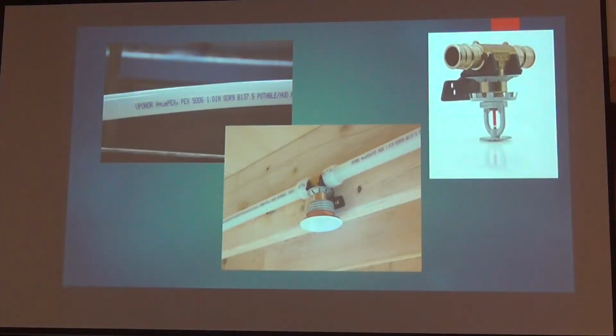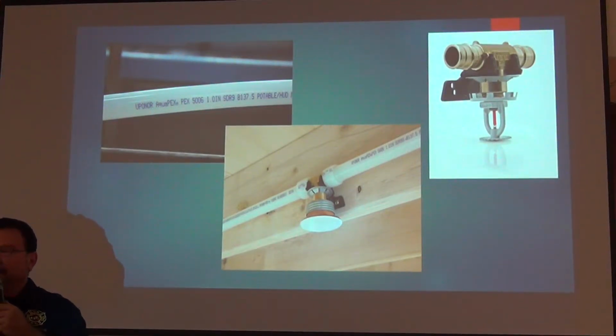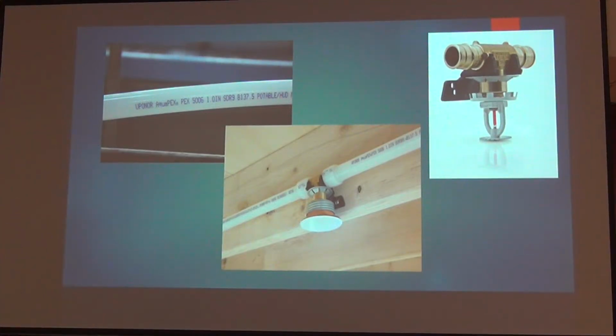All right, so Uponor is the manufacturer. Scott Deckrow helped me get that system going for the veteran. So they don't distribute for the sprinkler system anymore, but if you're going to have a multi-purpose system in your jurisdiction, Uponor will do the engineering. It costs, well, it used to cost $500. I don't know what it costs anymore because it's been quite a while since I've had that done. Another advantage to the multi-purpose system with this Class A PEX is if you're retrofitting a house, the runs in the wall to connect the inner and upper loop, you do not have to secure. They got some special approval for that. Kudos for them.